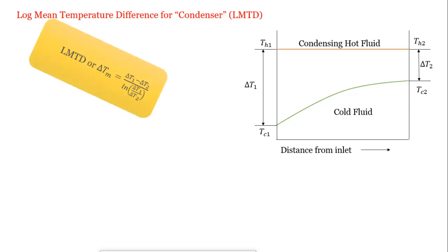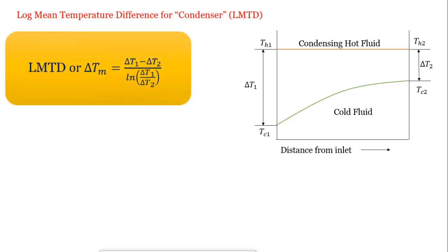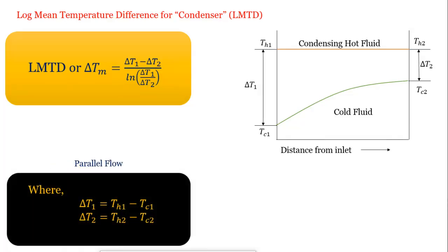We use the same formula for the log-mean temperature difference: LMTD equals delta T1 minus delta T2 divided by ln(delta T1/delta T2). If the condenser is in parallel flow, delta T1 equals TH1 minus TC1, and delta T2 equals TH2 minus TC2.